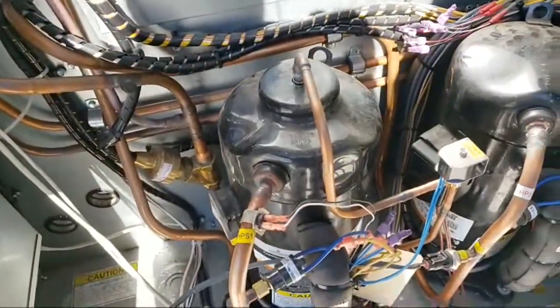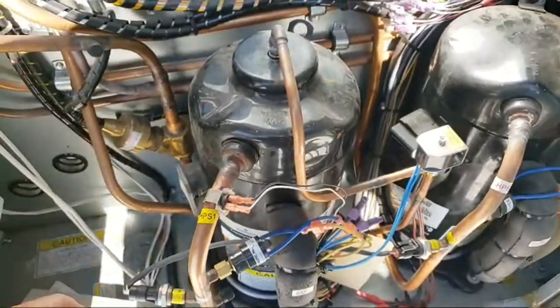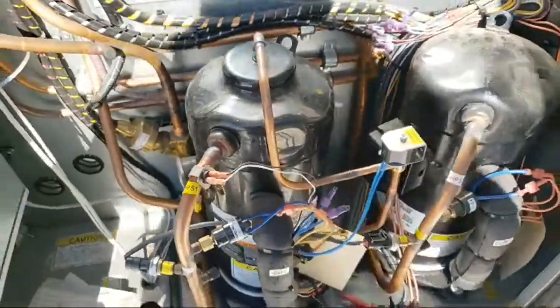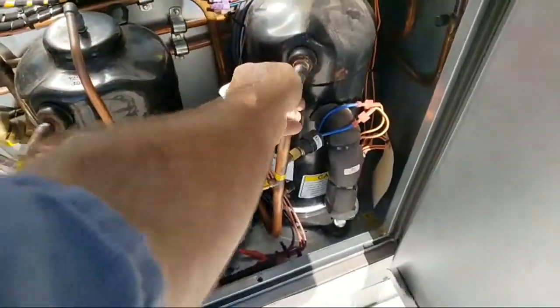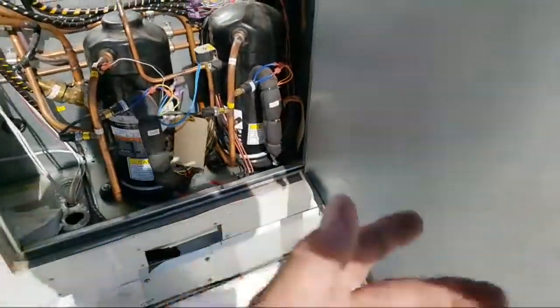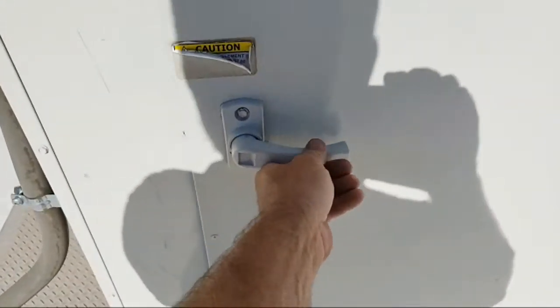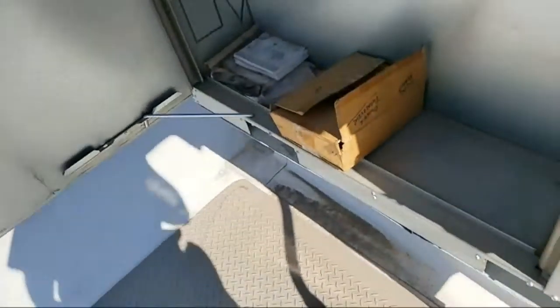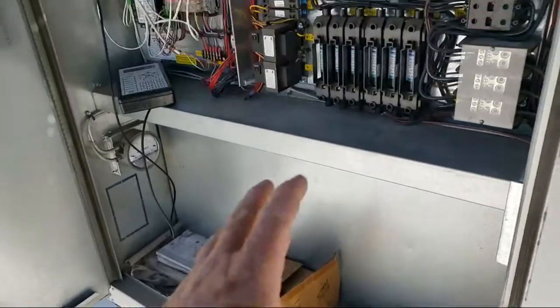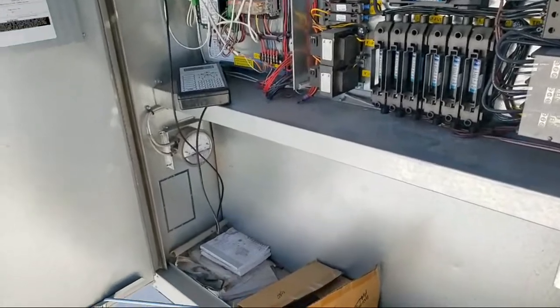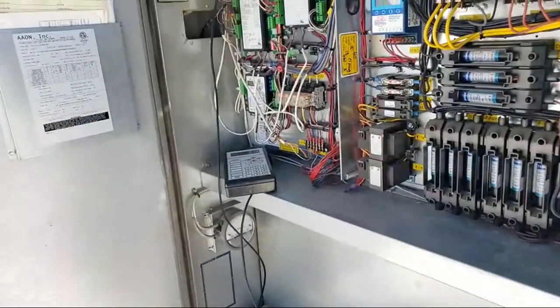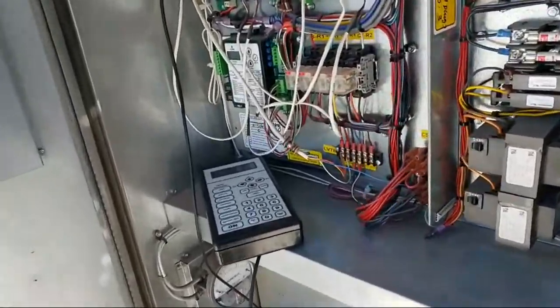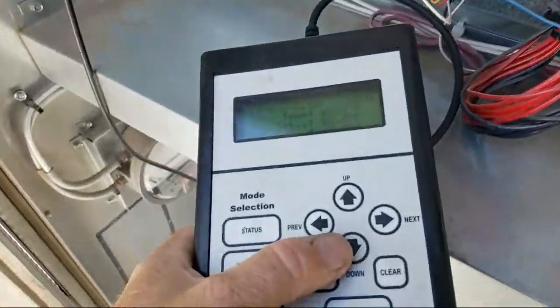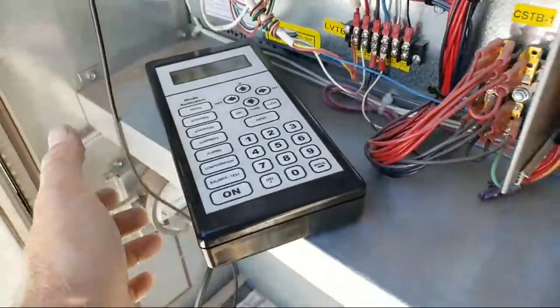So yeah, I don't know why, but when it was in reheat dehumidification control, most of the time it had the second compressor on. Because I guess it figures, let's get that coil really cold, but that's silly, you can't put that much heat back in. So the BTUs, the heat being removed with 2 compressors, 2 stages, was way more than the 1 stage of the reheat coil on compressor 1 only. So maybe there's somewhere in a setting to disable the second stage in reheat dehumidification mode. I don't know, I've never configured it that deep in one of these.